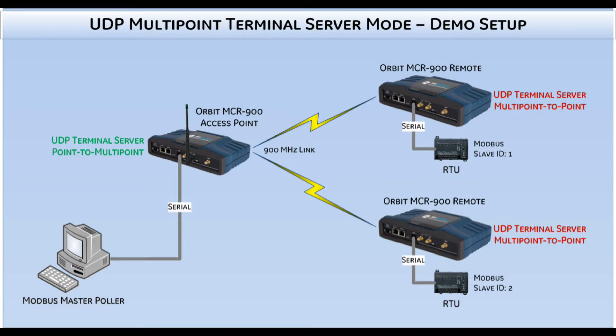Here is the setup that I will be demonstrating today. Using Orbit MCR900s, I have an access point with two connected remotes. Each Orbit remote has a Modbus RTU device off its COM1 serial port. For terminal servers, the access point will be configured for UDP point-to-multipoint, and the remotes will be UDP multipoint-to-point. This means that when the access point gets data on its serial port from the Modbus master, it will create a UDP packet and send it out to the multicast address. A static route was configured to direct how a multicast IP packet leaves the Orbit.